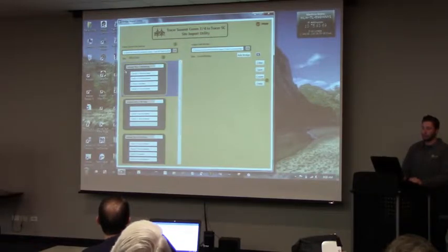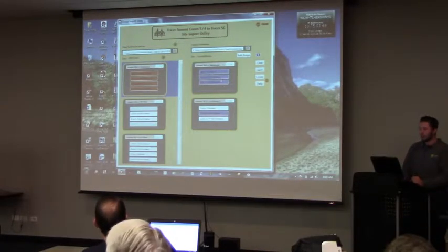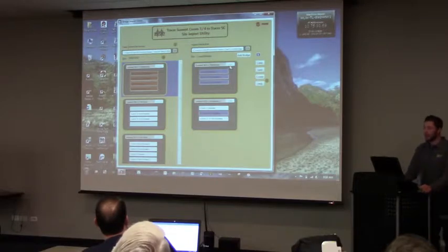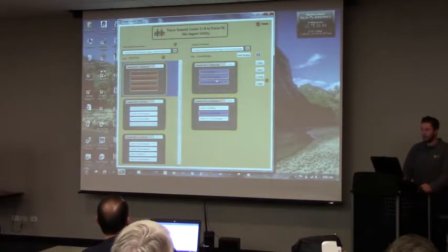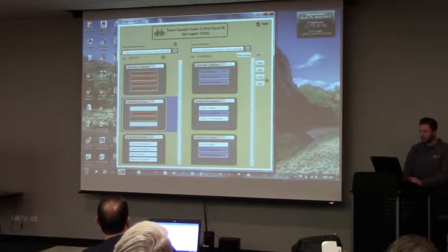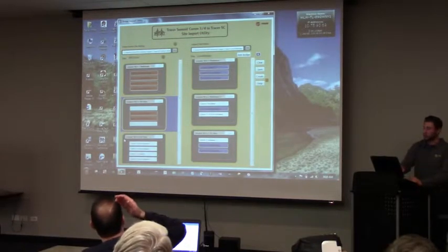So once we take one over here, you just drag it over, and you can see this one already created 2 because there's 3 COM4 links. So you can see your addresses right here as well. You have 128 and 129. These are what you need to address your bridges, so that way when the database goes in there, it gets pushed to these correct controllers here. And they tell you where the COM links are getting mapped to right here. And then you can just come over here and do another BCU. That one was just 1, because there's only 2 COM4 links. This one's going to create 2.